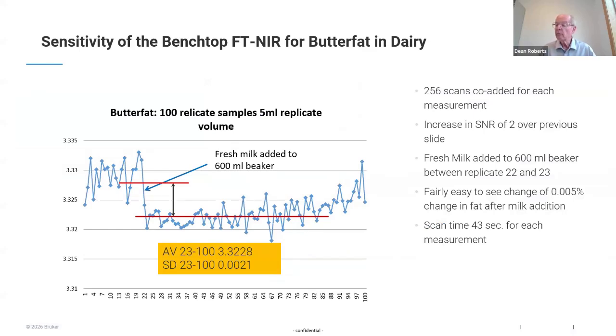But accuracy and repeatability obviously are not the same thing. So this is an experiment that we did on one of the MPAs where we took some samples, put it in a 600 ml beaker, and we started measuring replicate measurements. So each one of these dots is a 5 milliliter sample volume pumped between the measurement cycles on the instrument. And you can look at it, and we've got about 0.007 repeatability right up to where we added the fresh milk to the beaker. Now, this beaker was sitting on the apron of the instrument.